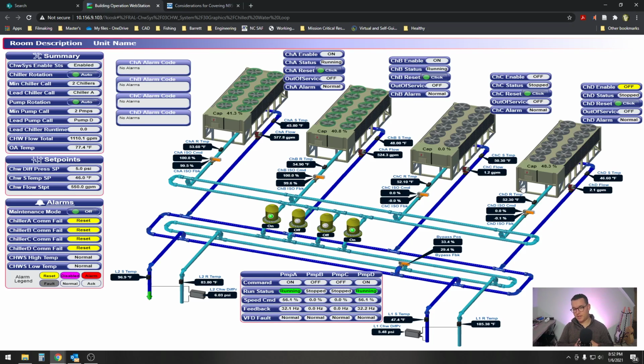So in summary, again, the 3 things that we care about are system flow, minimum chiller flow, and the supply temperature, and what controls those. What controls the flow through the entire system is this differential set point. As the sensor reads lower, the pumps are going to kick on higher. As they read higher, the pump speed's going to go back down. That's its sole mission. Then that's the total flow through the system.